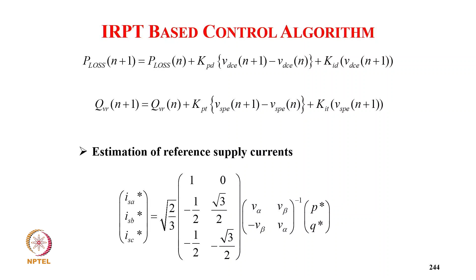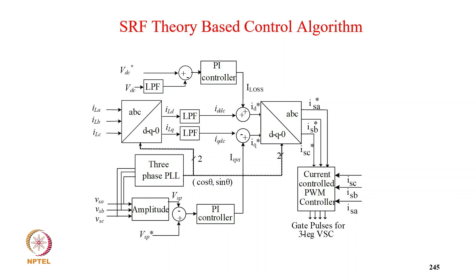So this is of course the synchronous reference frame theory algorithm. Here again is the DC link voltage control. Similarly, after the DC link voltage is passed through a low pass filter and PI control, we get the loss component. Then from the load current and from the template, which we get from the PLL, we get the ILD, ILQ fundamental, and from which the low pass filter gives the DC component. So we get the total active power component and reactive power. From the voltage PI controller we get another component. From this we get the reactive current to be in the supply system, and taking the template we are able to get the three-phase grid current, taking feedback current using current control to give a switching signal to the voltage source converter acting as a D-STATCOM.